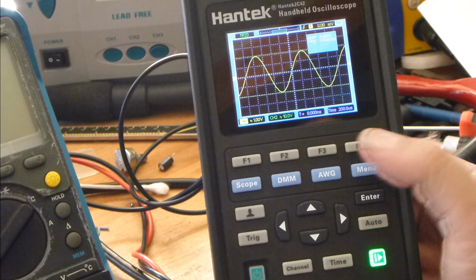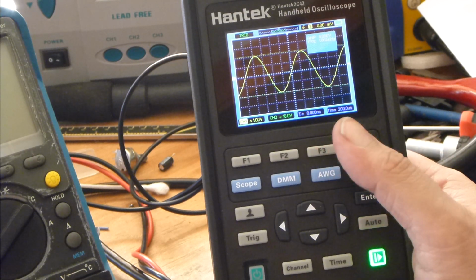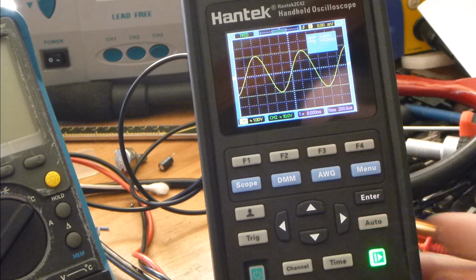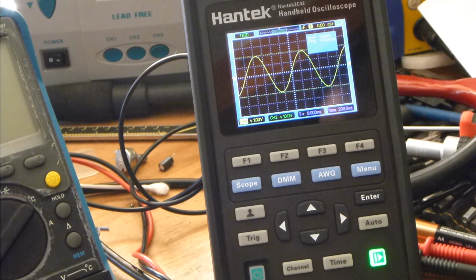Oh, the calibration. Just checking my notes real quick. The calibration, I calibrated it 3 times, turning it off, turning it back on, and then running the calibration. All 3 of those times I used a stopwatch and then averaged them together. And the average that I got was 2 minutes 17 seconds. Excuse me, 2 minutes and 17.656 was the average. And literally it was like 217.61, 217.69. There was probably less. Probably my finger hitting the buttons was more of an error than anything else. So I would bet you it's pretty darn close every time it runs a calibration.